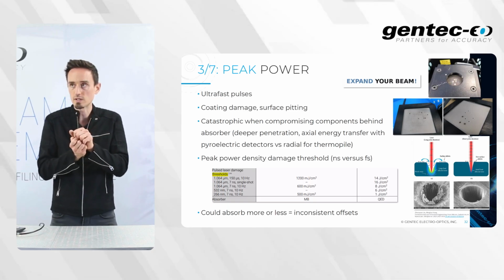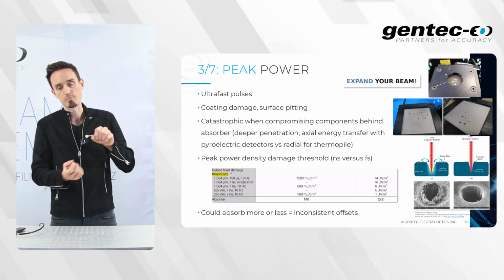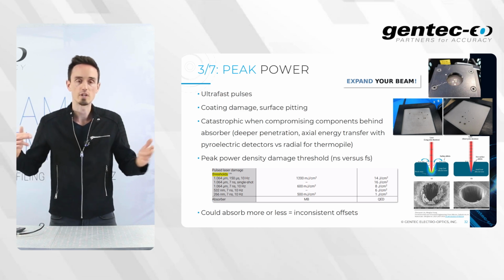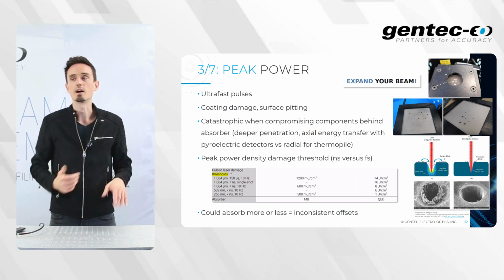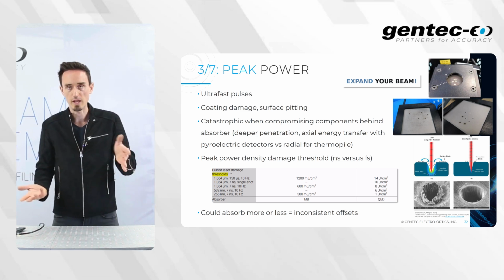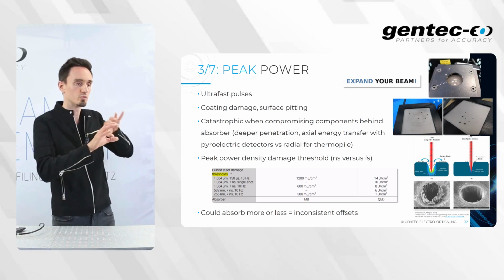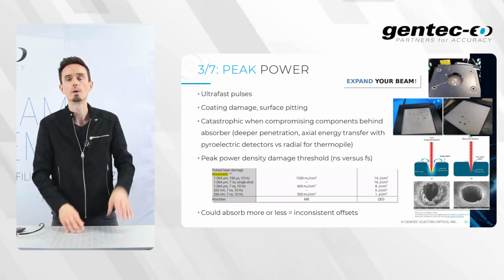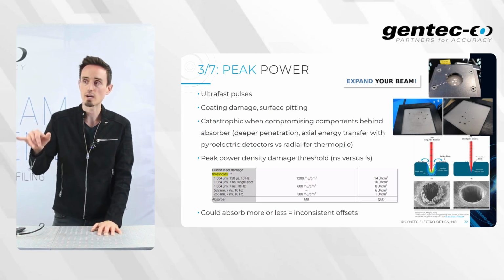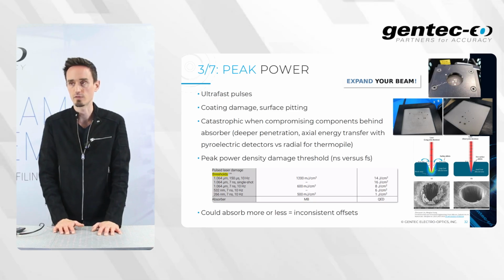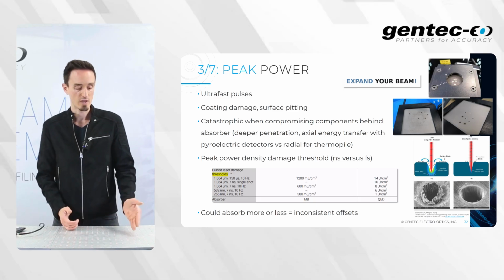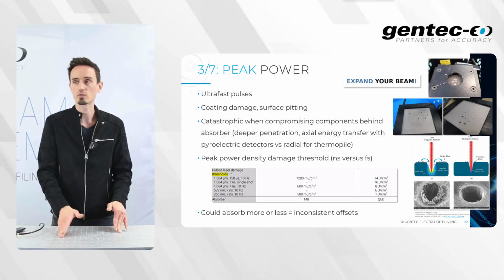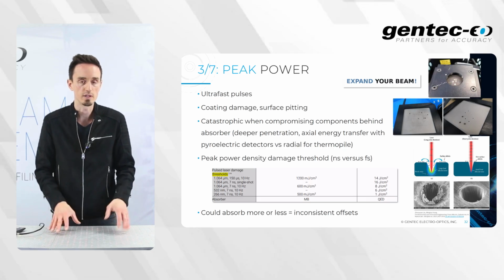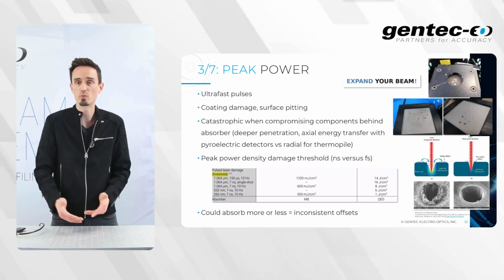For pyroelectric detectors, as you can see here, the energy is deposited as an axial transfer, so it goes deeper. And for thermopile detectors, it goes radial, so it is spread out. It's pretty much diffused. So as you can see on the right here, this is a good illustration of, for the same energy level again, a nanosecond versus a femtosecond pulse having a different kind of impact, and the cut will be sharper with a femtosecond laser.